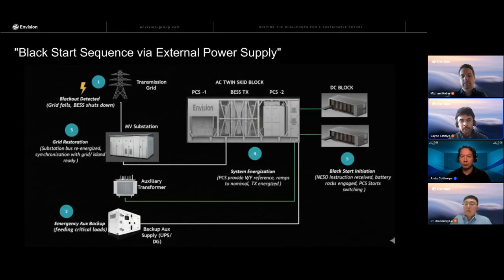So the auxiliary backup is one of the key things in how we design the system, and we can use either a diesel generator or a small backup inverter, which takes the DC source from the batteries and feeds the in-house auxiliary loads.